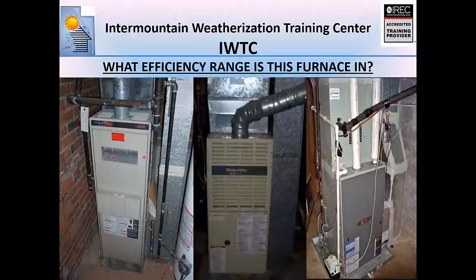So that's one quick way, just by visually looking at a furnace, you can determine generally what efficiency range it falls into. If it's got some kind of draft hood, and sometimes you'll even see them up here on some older furnaces, it almost resembles what you see on a water heater. There'll be a draft hood up here. It's not quite as common as this guy here. If there's no draft hood but a louvered door, you're somewhere in the 80% efficiency range. No louvered doors, plastic flues, 90 percentile range.